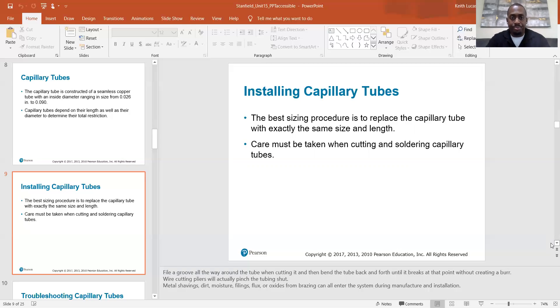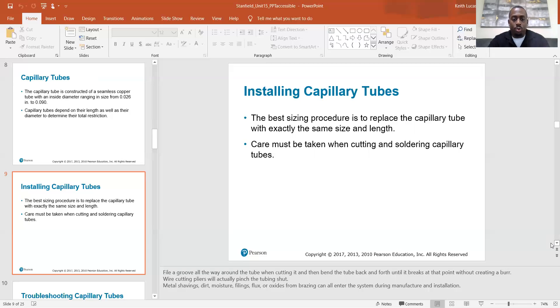When installing capillary tubes, the best sizing procedure is to replace the cap tube with exactly the same size and length. Care must be taken when cutting and soldering — you definitely don't want to kink or pinch the capillary tube, or your metering device will not operate. To cut it, file a groove all the way around the tube and then bend it back and forth until it breaks at that point without creating a burr. Wire cutting pliers will actually pinch the tubing shut.